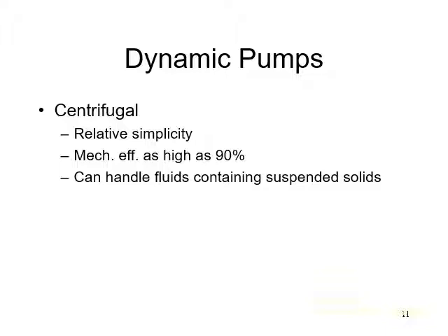If suspended particles are present in a fluid, that may not cause any problems in a centrifugal pump. But in a displacement type of pump, these suspended particles may get stuck in the gap between the piston and cylinder. That will score the piston and cylinder surface, and also damage the piston surface.